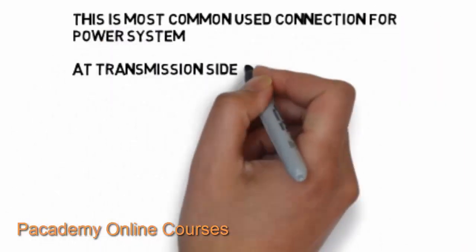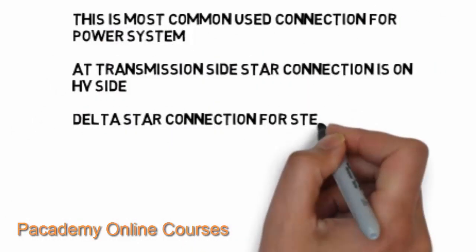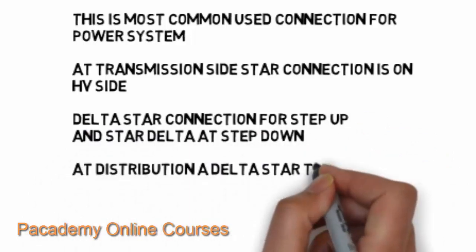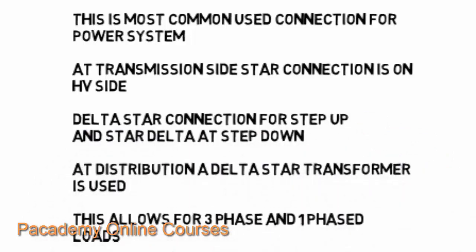The star-delta connection is the most commonly used connection for power systems. At the transmission side, the star connection is on the high voltage side and the delta connection is on the low voltage side. The delta-star connection is used for step-up and star-delta connection is used at the step-down end of the transmission system.